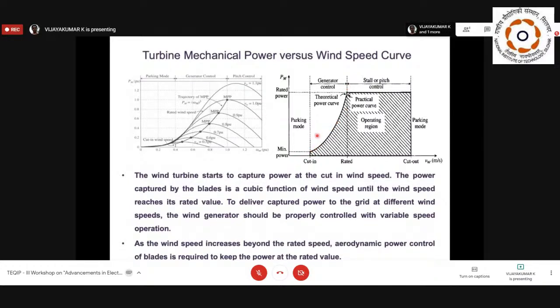Only in this region, from this point to this point, you have to implement the maximum power point tracking algorithms. So from cut-in speed to rated speed, right? This is what we get from this curve. From this point to this point, they call it generator control. Why they call it generator control: as electrical engineers, it is easy for us to control the speed of the machine. If you control the speed of the machine, you can control the speed of the turbine, because the machine is coupled with the turbine. So it's an indirect control. You are indirectly controlling the speed of the turbine by controlling the speed of the electrical machine, right?